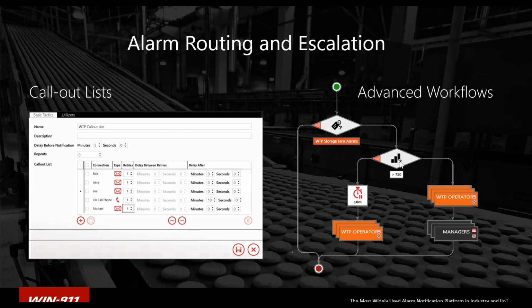If the alarm is over 750, we then move to the right, and we notify a group of people wearing this water treatment plant operator's role. We're also going to notify all people in our phone book that have a manager's role. If it was less than 750, we would have moved out to the left here. We would have had a 10-minute delay, and then if the alarm was still active after those 10 minutes, we would just notify the operators. So those are two different ways of setting up the escalation or call routing for the alarms.